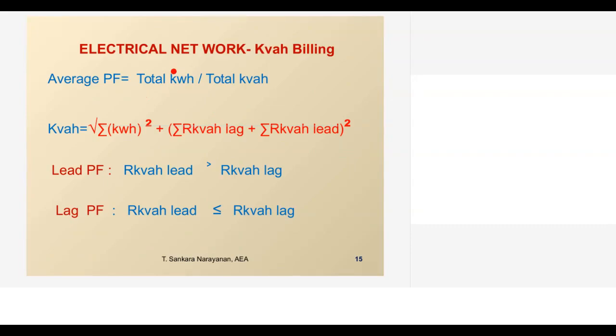Then, electrical network kVAh billing, we have already seen. Earlier we were taking the average PF, total kWh by total kVAh. So now kVAh is calculated as the square root of kWh squared plus (RkVAh lag plus RkVAh lead) squared. So now the calculation is for real-time power factor. RkVAh lag is how much the industry has taken, RkVAh lead is how much it has taken. Based on that, kVAh is calculated, not based on the old total kVAh. So now the kVAh billing meters have been replaced. They can monitor the kVAh lead and lag. The power factor is decided as a leading power factor if RkVAh lead is greater than lag. It is a lagging power factor if RkVAh lead is less than lag.